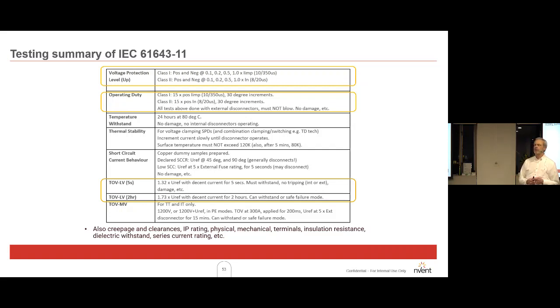Class 1 is used for rating surge diverters where there's a direct strike lightning protection system installed on buildings or where you have extreme exposure. There's more energy in a 10 by 350 microsecond waveform than there is in the 8 by 20. Class 2 is used for lower exposure main switchboards and for distribution boards.